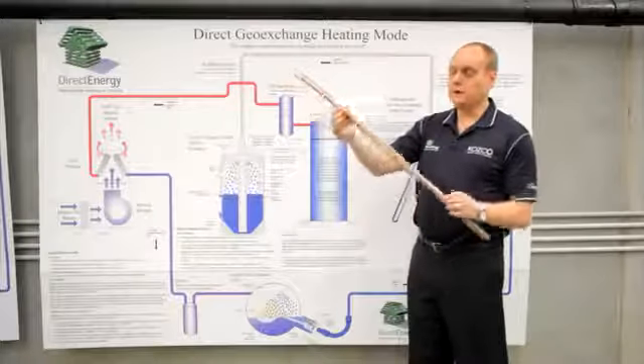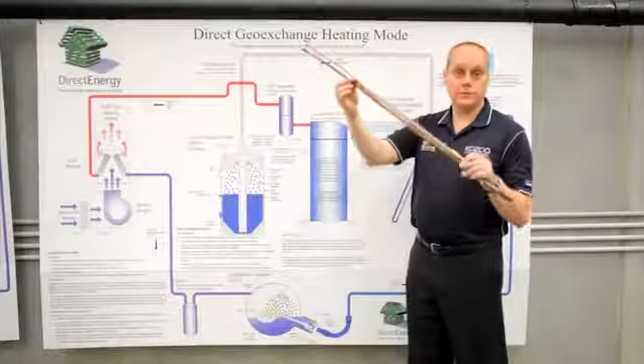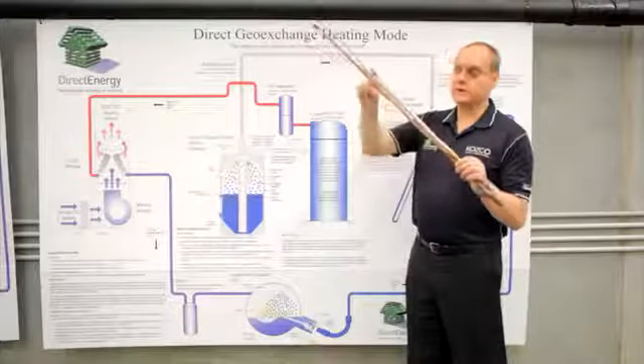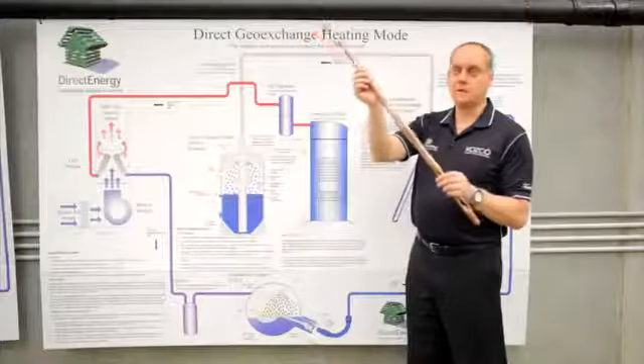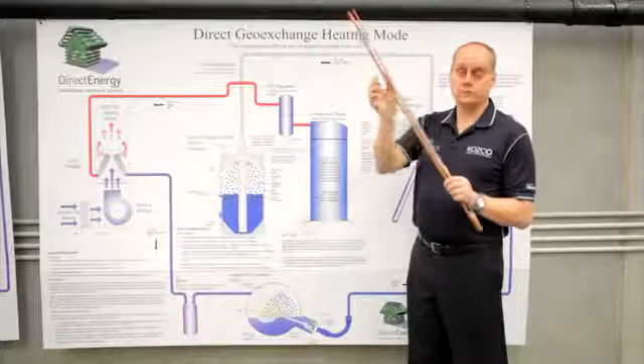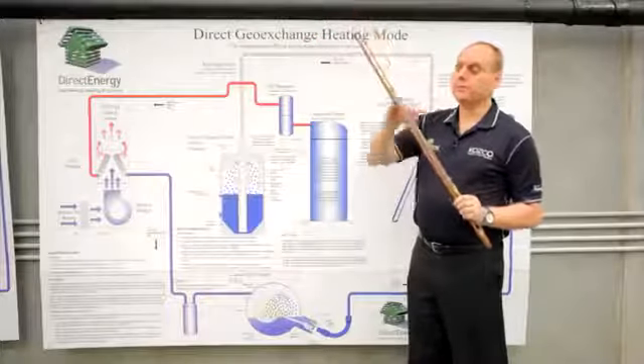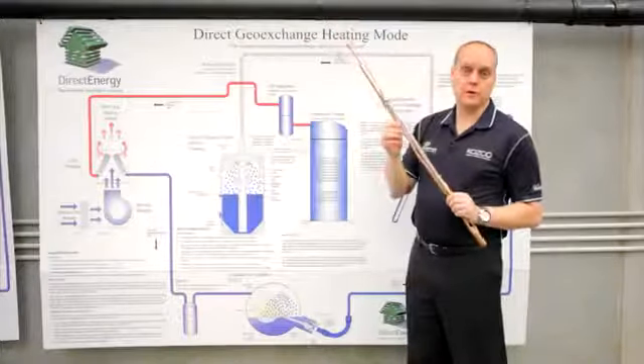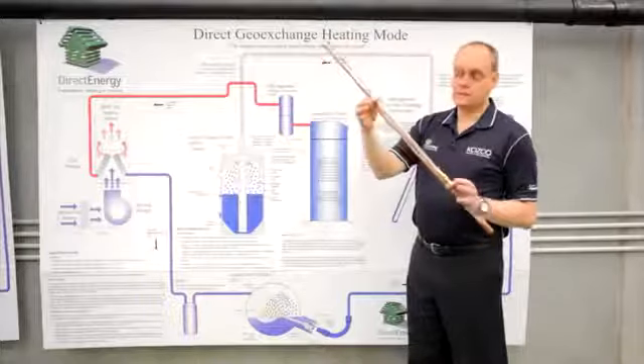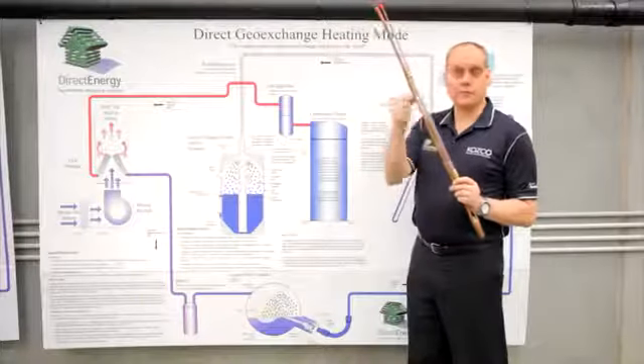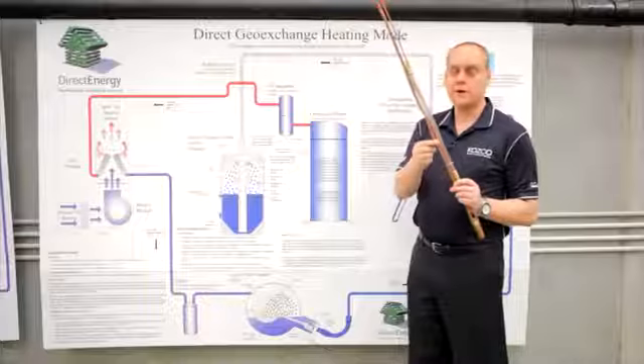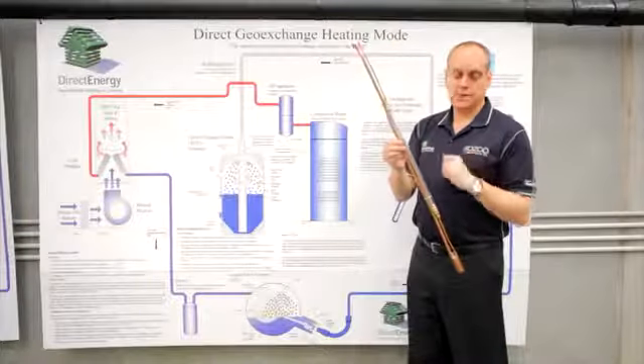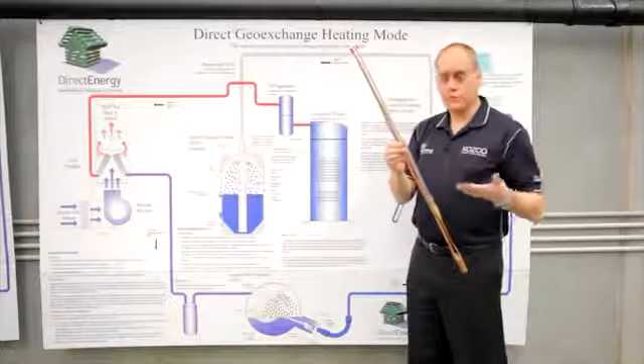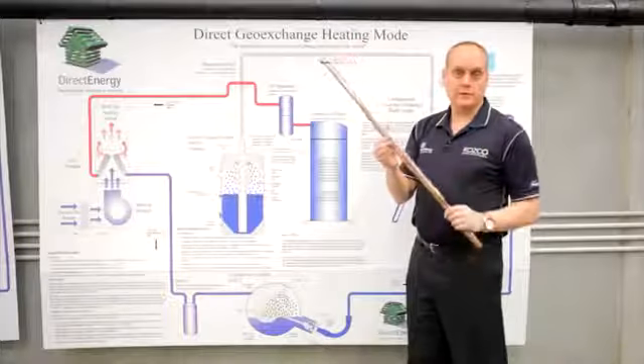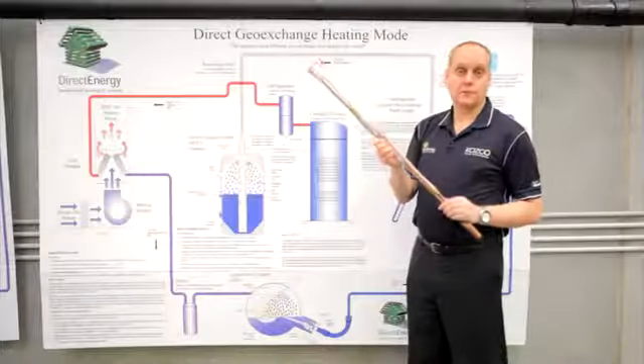The condensate for the top 15 metres of a 30 metre loop has an insulated tubing on it that allows the ground portion of the system to bring liquid refrigerant back to the heat pump for cooling purposes. This insulation reduces the chance of flashing from the hot refrigerant coming down on the vapour side, and also stops the constant ground temperature's warmth from providing thermal energy back into that condensed refrigerant.